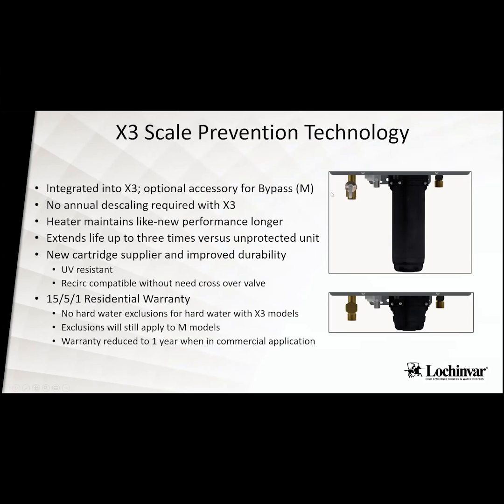As you'll see right here on the hot side coming out, there is a pressure valve that comes inside the box. It has a little port there that just screws into it. If you buy it in the M version, there's a cap that comes already installed on it there. So you do not need to have isolation valves on this.